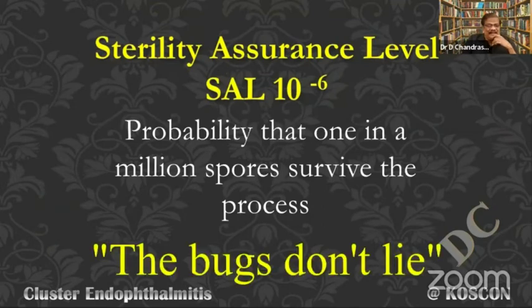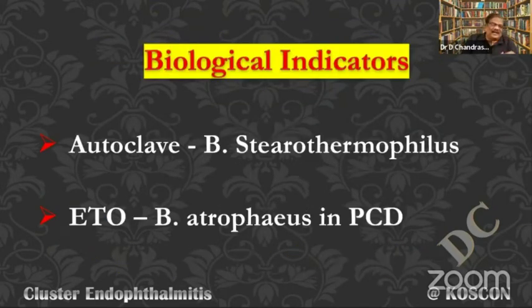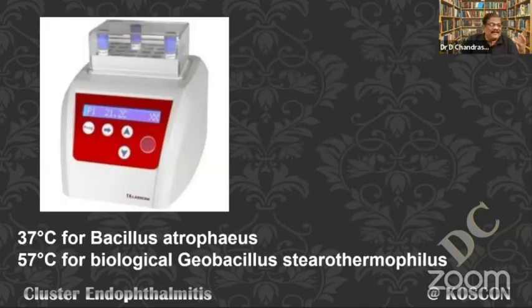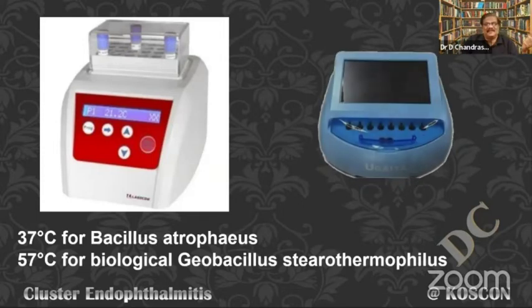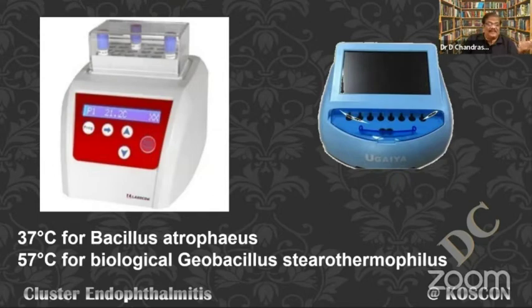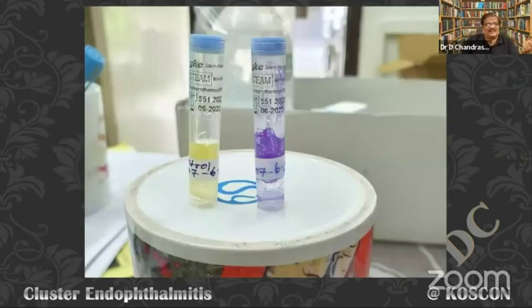The biological indicator is very important. For autoclaves we use stearothermophilus geobacillus, and Bacillus atrophaeus for ETO. These are incubated at 37 degrees for atrophaeus and 57 degrees for stearothermophilus. Now rapid incubators are available, letting us know results based on enzyme reaction within 2 to 3 hours. The color change requires a control, and these are the gold standards for biological validation.